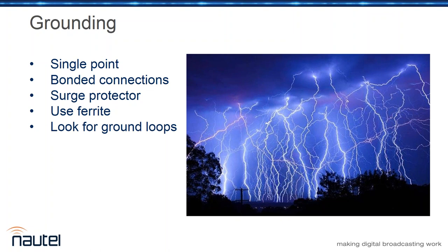Single point grounding, try to avoid ground loops. Any piece of equipment should have, where possible, one ground connection and one ground connection only. Obviously, in real life, that's not going to be the case. You're going to have a transmitter, for example, have shielded wire coming in with ground connections. You'll have conduit coming in, which is usually made of some metallic material. You'll have the ground strap, you'll have the AC safety ground.